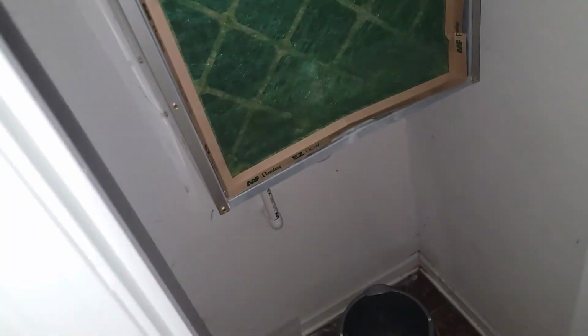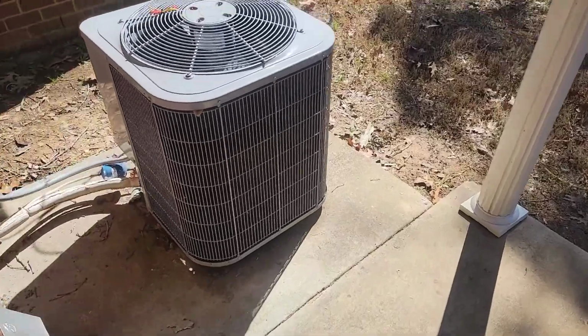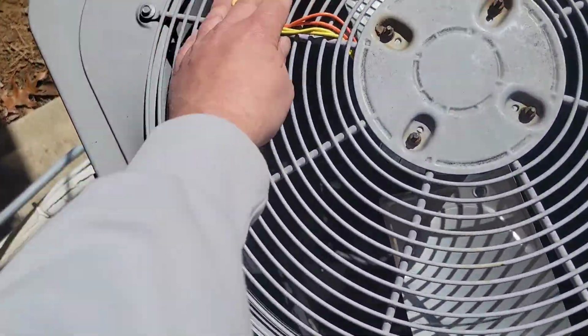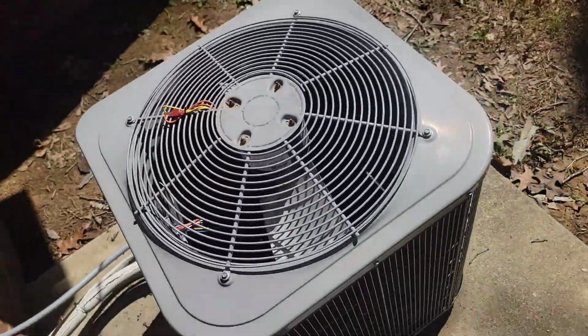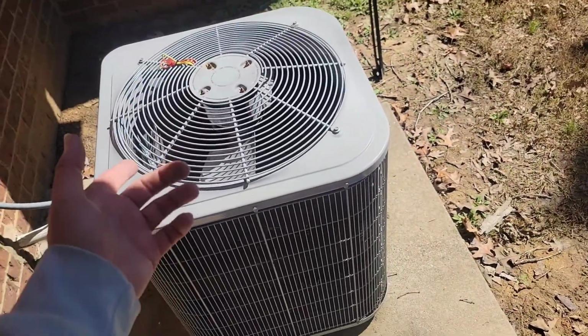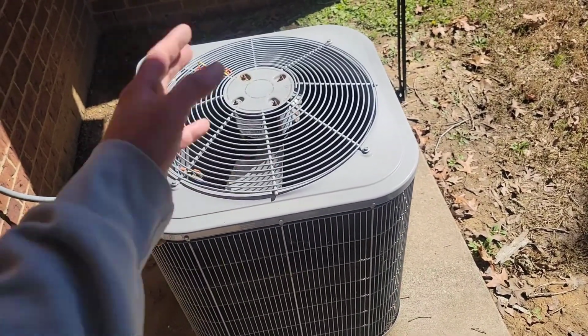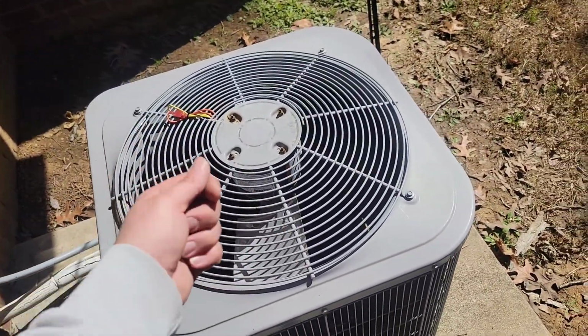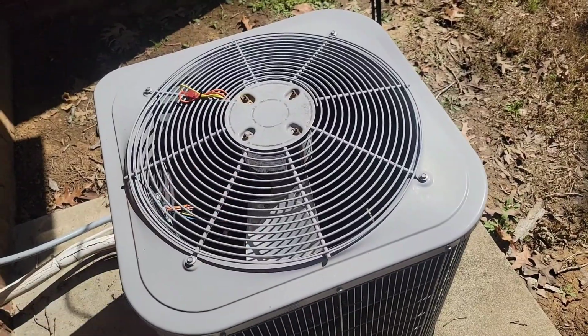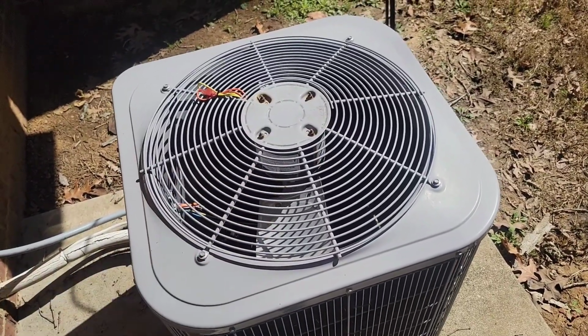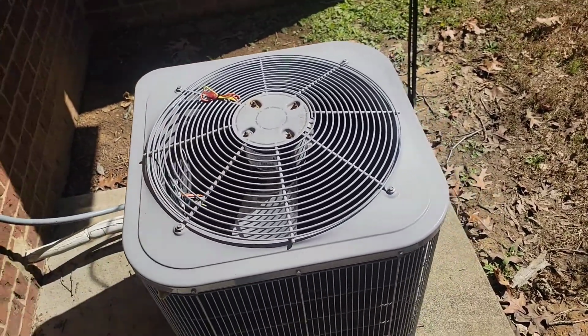And you can see there's been some water damage. So this drain has definitely been stopped up in the past. So you can see somebody's put a rescue motor on here. Outdoor fan motors go bad, so if you're going to take the top off to check for leaks, make sure you check the motor bearings. Make sure the bearings are good, or if they have slack, then you may need to go ahead and order a motor.